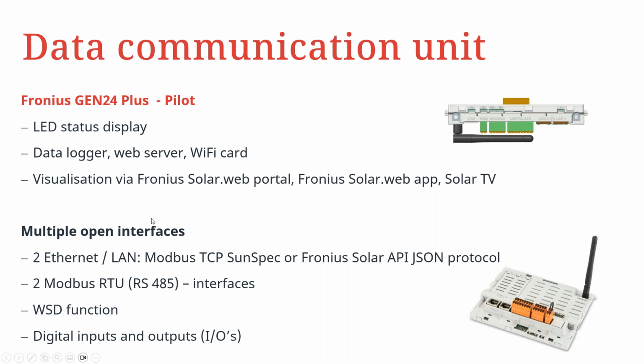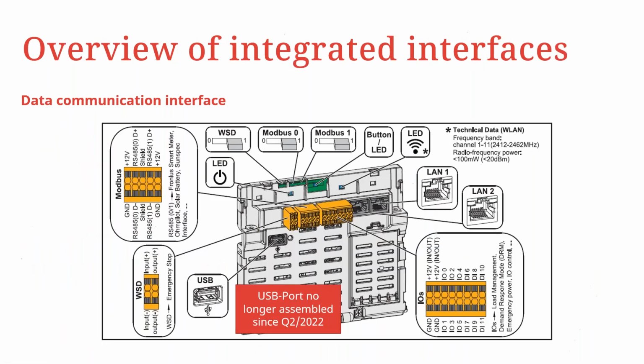Integrated also in this Pilot are multiple open interfaces, which include 2 Ethernet or LAN ports, usually called Modbus TCP, which is also used for Fronius Solar API or JSON protocol communication. We have 2 Modbus RTU interfaces, in comparison to the Data Manager that has 1. So this has 2 Modbus RTU interfaces using the RS485 communication protocol. And then we have a peculiar feature, which is the wired shutdown function. This will be discussed subsequently in the coming slides. And then, of course, we also have the digital input-output ports that can be used to implement energy management processes. So let's have a brief overview of the integrated interfaces.